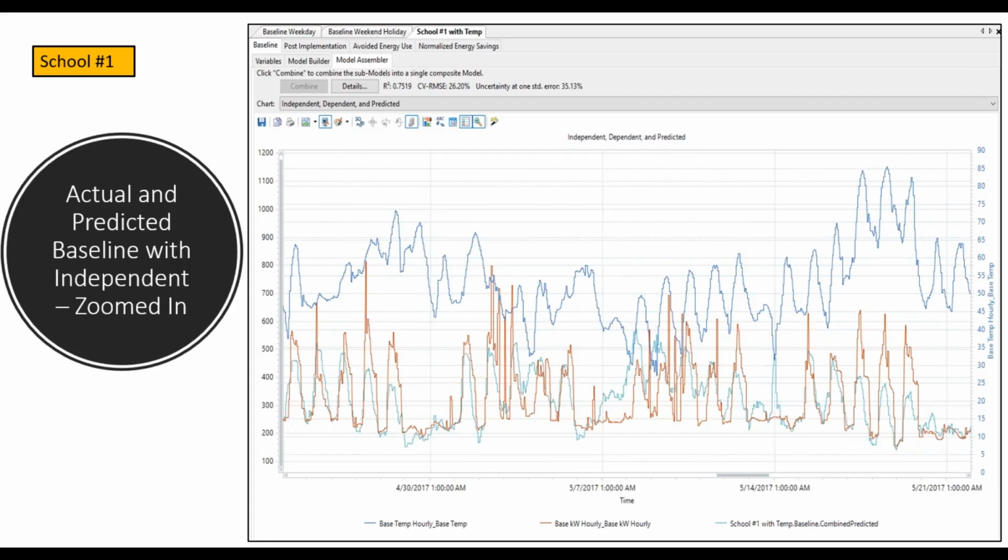It is generally going to somewhat underpredict spikes. Almost any model is going to do that because it's going to come to the average or the typical value. This building, I think, was an odd electrically heated building, so it's spikier than most, but you can see that the model is doing a pretty poor job of hitting these really high peaks.